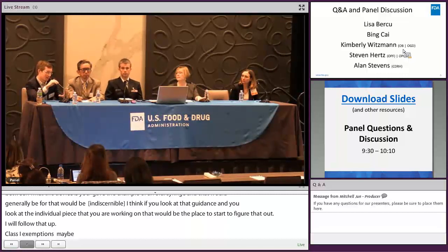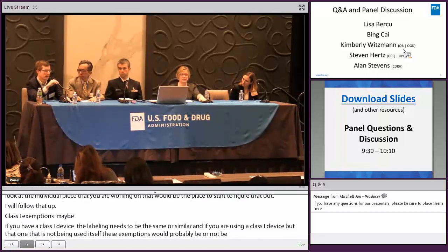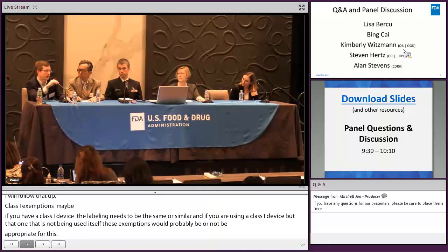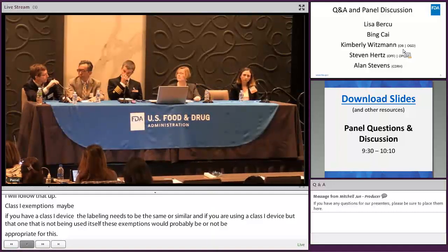In summary, Class 1 exemptions do exist and are described within either the guidance. There's an alternative mechanisms for GMPs federal notice that was published last year. So I think that has more information about Class 1 exemptions for combos.